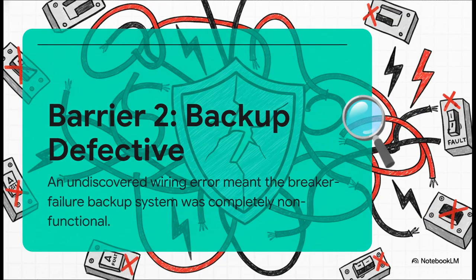Okay, so primary protection fails. That's what the backup is for, right? There's a system called breaker failure protection that's supposed to see that the breaker didn't open and then trip all the other breakers to isolate the problem. But it never activated. The DNV report found a latent wiring error in the system. It had probably been sitting there for who knows how long, completely unnoticed, because the quality control tests hadn't been fully completed. The backup system was, for all intents and purposes, dead.